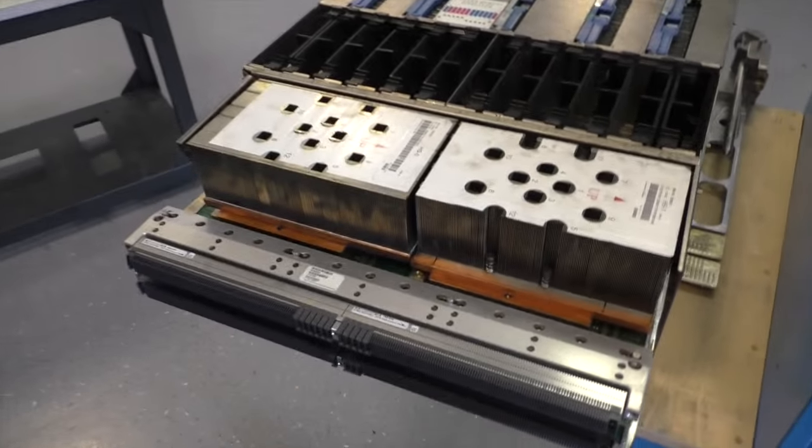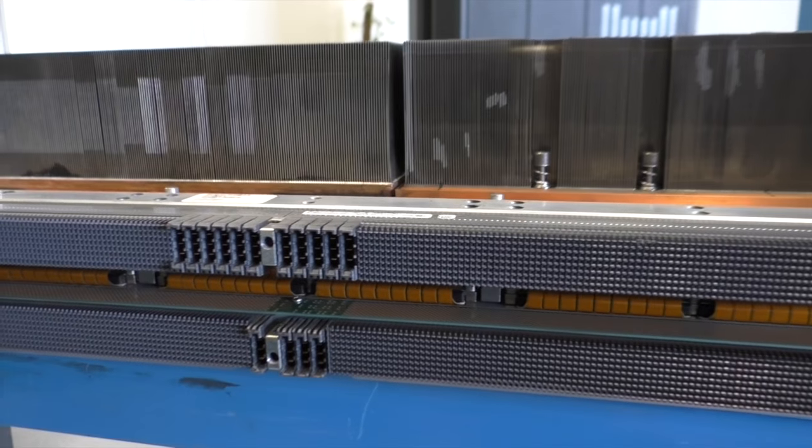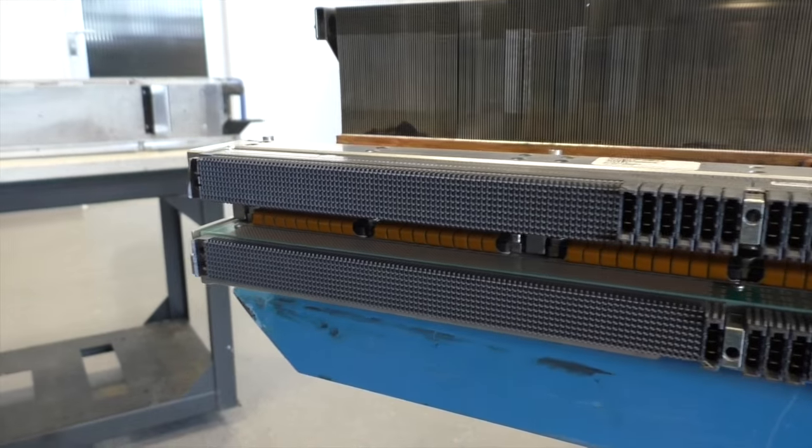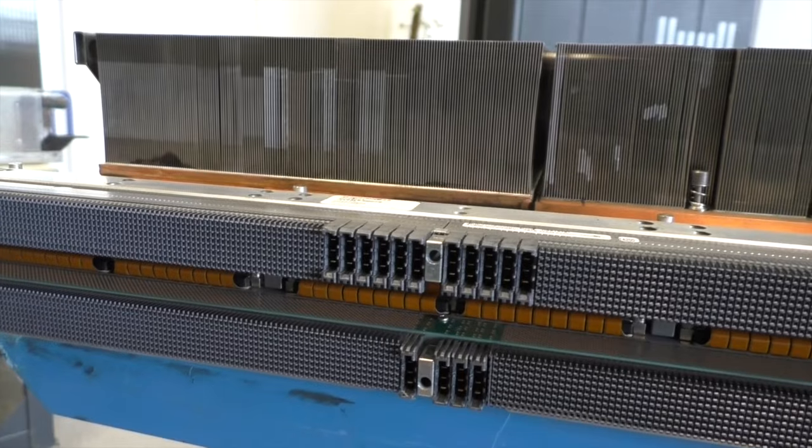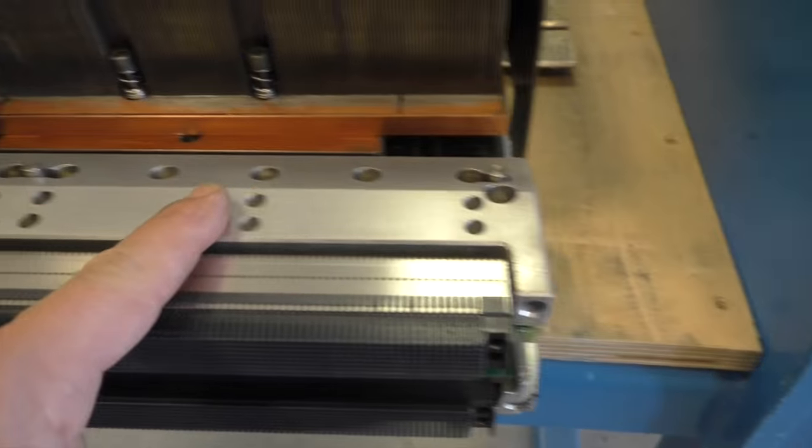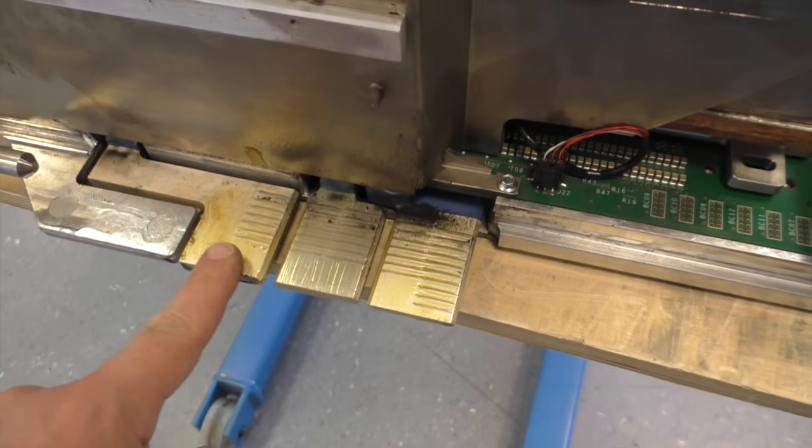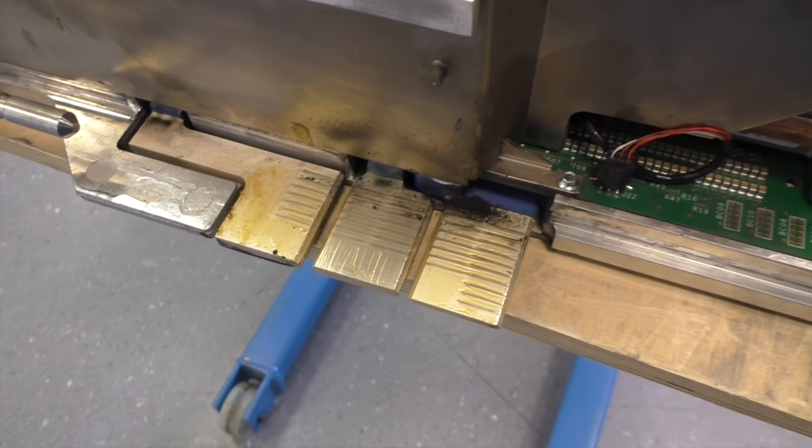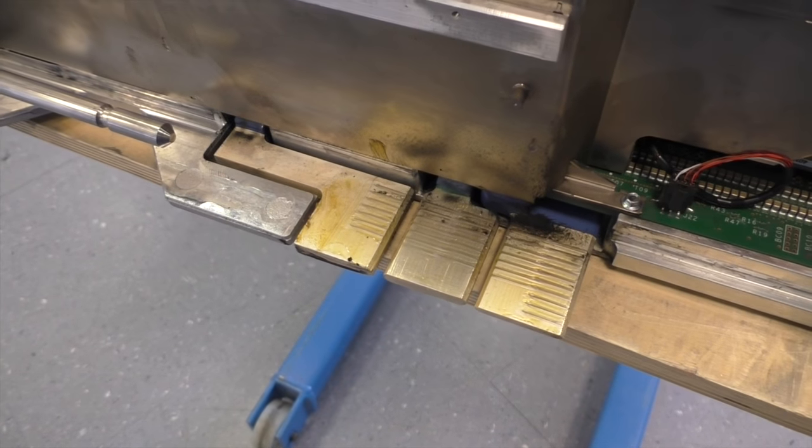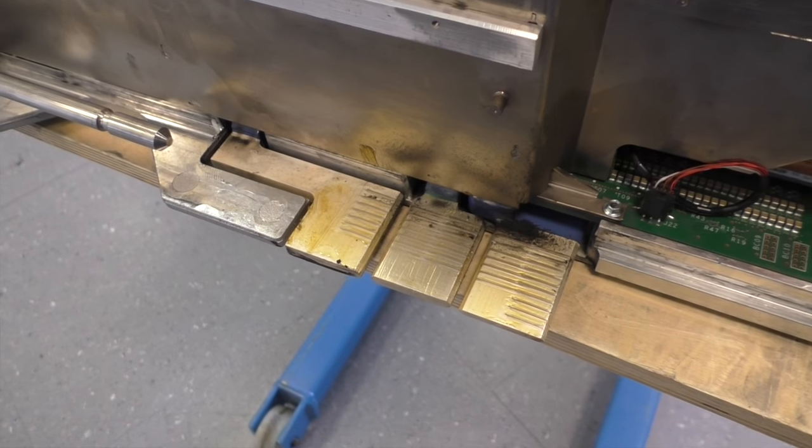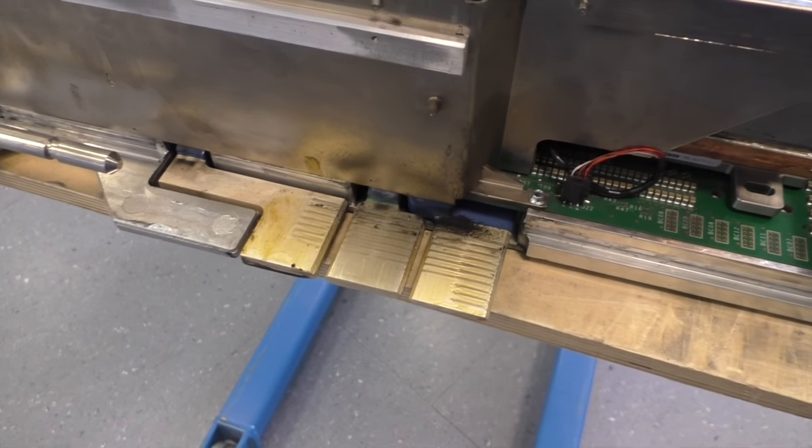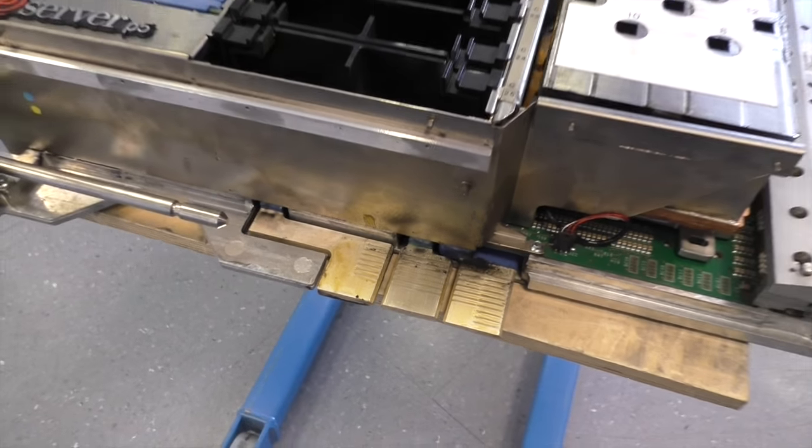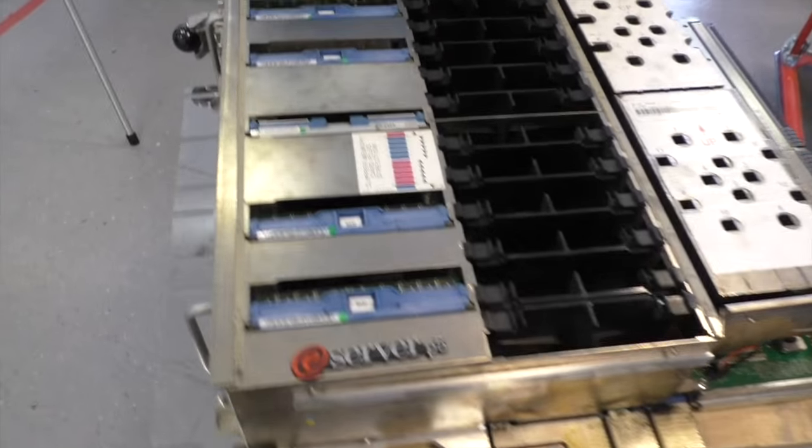An impressive part is this connector array here. You can see there are thousands of contacts, power contacts here in the center for the smaller power supplies, massive aluminum bracket here. Then on the side we have power contacts for the heavy, I don't know how many amps power supply. On the Z9 there was a 1 volt 800 amp power supply which I will present in another video. I assume these connectors here are made for 1000 amps or something like that.